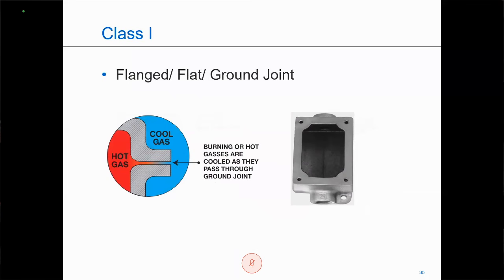Now, a very popular unit also in hazardous location areas is the flange joint, the ground joint. This is popular with control stations, motor starters, panel boards, these types of products in hazardous location areas. And with this particular product, rather than the thread being the flame path, the flange is the flame path. So we're going to make sure that when we're installing this product, the flange is free and clear of any dirt, any damage, and we're going to want to make sure we have all bolts installed. And that I can't say enough, all bolts installed.